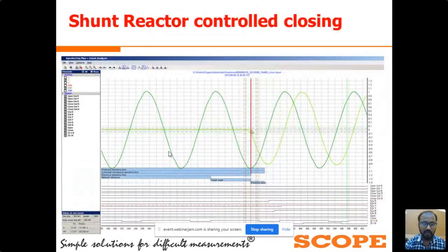So now we will see the actual waveform for the shunt reactor controlled closing. This is the actual waveform that we have downloaded from the control switching device. Here we can see the result that we have achieved with the control switching device. This is the system voltage waveform, and the waveform started from this cursor point. This is the current waveform. As we have already discussed, for the closing of shunt reactor, we are taking the reference of voltage signal. We are targeting the voltage peak points.